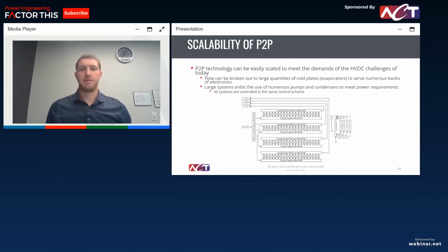And then looking at scalability, pump two-phase is great for scaling to large systems. We have an application we're working on now that has 400 cold plates. So you can have one system feeding a large quantity of cold plates, a large quantity of manifolds, and multiple different electrical systems. Especially as you scale up, it can oftentimes be more advantageous cost-wise than having one small system for each individual electrical system. So you can have all your pumps and your fans and condensers all tied into the same control scheme, all your fluid running through the same system, and then broken out between all the different banks of electronics.